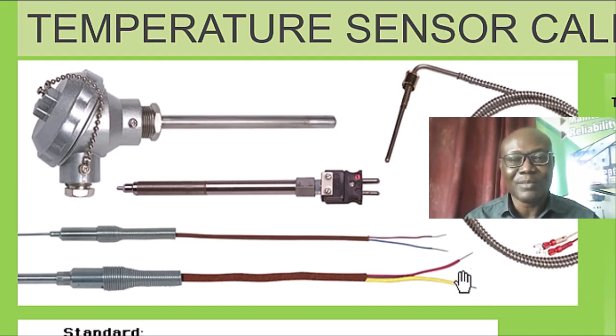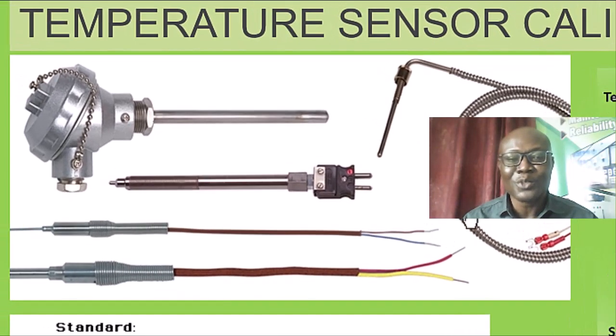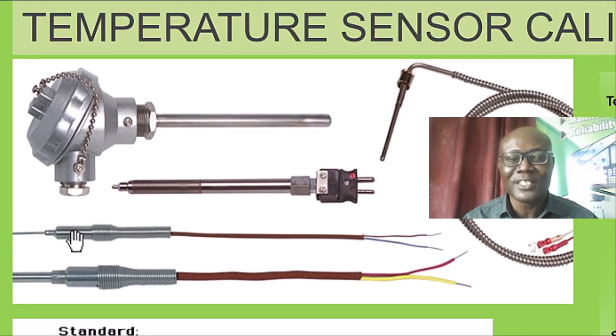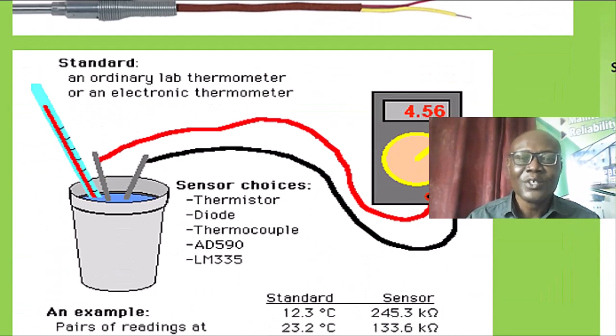these two terminals. Okay, so what we want to do during calibration is to subject these thermocouples or these temperature sensors to those temperatures and see if we will have those outputs from these terminals. If we have the output and they are within tolerable limits, then we can continue using the instruments or the sensors. But if they are not, we change them altogether. Okay, so we'll just look at it.